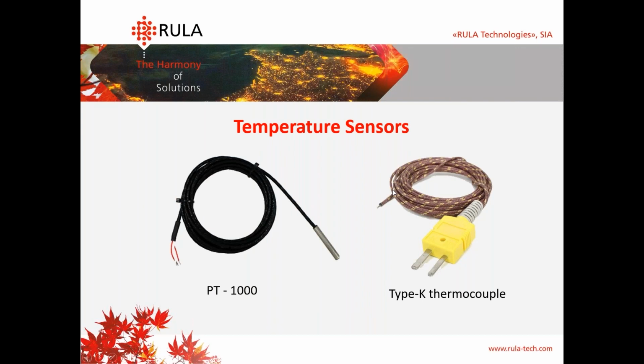In RLC21M, we also can connect temperature sensors. We can use a type K thermocouple or a PT1000 temperature sensor. They can be connected on the bottom, on the back side of the controller. And we can display temperature graphs on the screen.